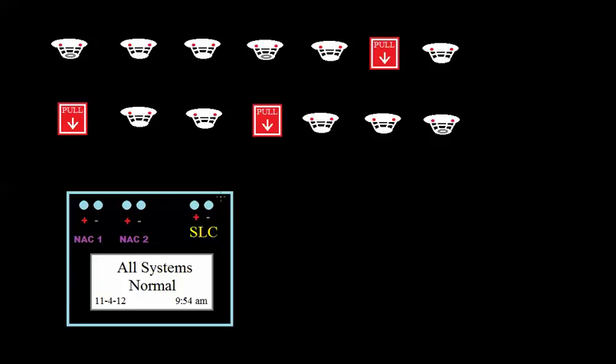There are limits to how many devices can be on one of these, and that's panel specific, so it would depend on what kind of panel you're dealing with. But it's usually around, well, it totally varies. But let's say for our purposes I could fit 100 detectors on here and 100 modules. The difference between a detector and a module: a detector would be an addressable smoke detector, heat detector, duct detector, possibly, I think that's probably about it.